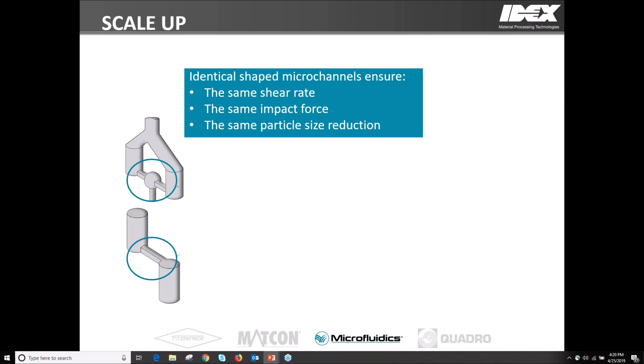So this fixed geometry interaction chamber comes in multiple shapes and sizes, including the Y and the Z type that you see here. The Y type is primarily used for liquid to liquid only applications, such as nanoemulsions, as the two streams will impinge upon each other, forming those very small uniform droplets. And the Z-type chamber is great for any application that contains any solids where the impact zone would be up against the wall. Our equipment is great for continuous processing. It can handle very high viscosities and solid content as well. But more importantly, it also can work with a wide range of temperatures.